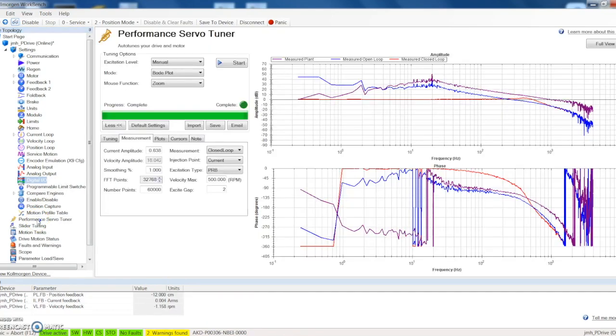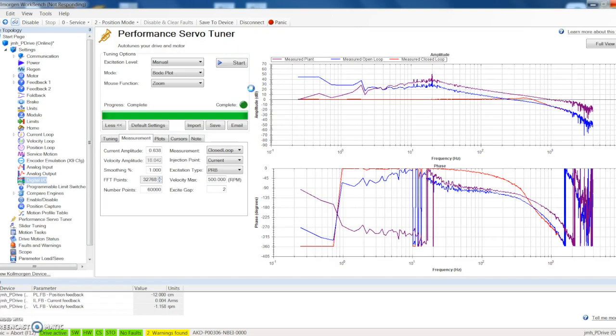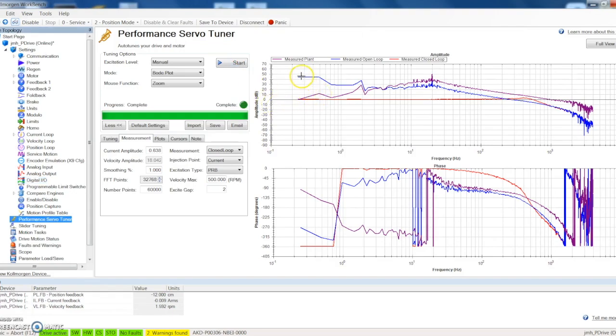Performance servo tuner: this is a really nice feature that once the motor is connected to all of the mechanics that it's going to be driving, this will allow the servo motor to go out and tune itself. So all you really have to do is come in here and push start and it will create a Bode plot and tune the servo motor to the mechanics of the system.